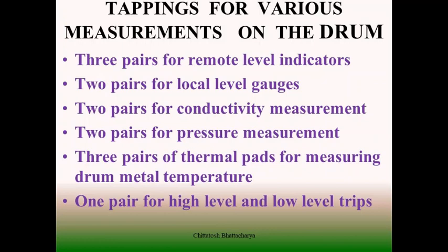Besides all these arrangements, there are various tappings taken from the drum, and these tappings are necessary for safeguarding the drum itself as well as to monitor the water quality, steam quality, and water-steam level within the drum, so that we can have control over the entire steam generating process, because feed water flow and steam flow outlet of the boiler, these two are getting balanced by the drum level. So drum level indicates the balance between feed water flow and steam flow.